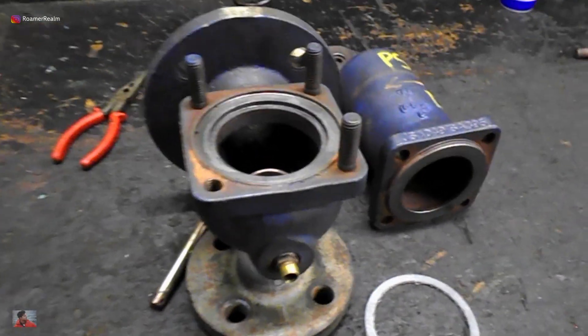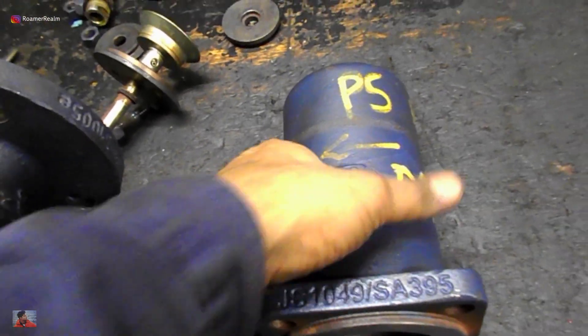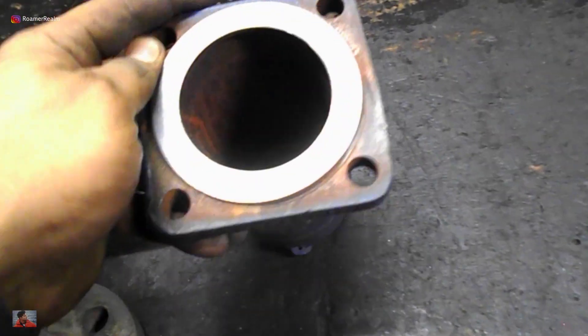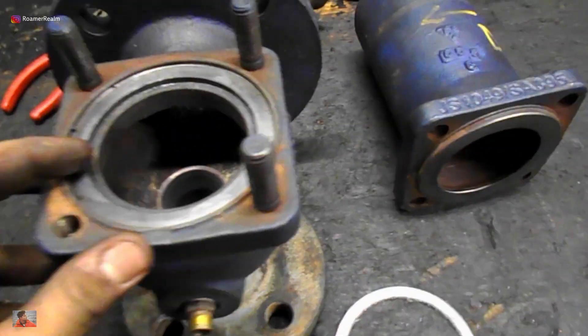Each of the four generators on the ship are rated 4 megawatts, and their exhaust gases pass through an exhaust gas economizer. This dismantled safety valve is from the port side economizer. The first step is to carry out a visual inspection to determine the condition for any clear signs of damage or leak.